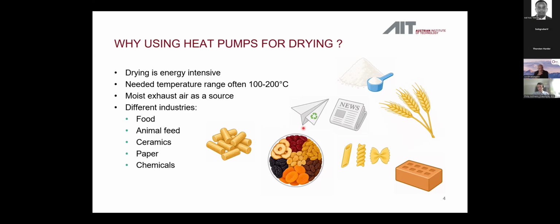The needed temperatures for drying processes often range between 100 and 200 degrees Celsius, which fits market available heat pumps. And the source for the heat pump is already there, because you can use the moist exhaust of the drying process as the source of the heat pump, which is advantageous because the source is then automatically available at the same time you need the energy for the drying process, and also at the same location.